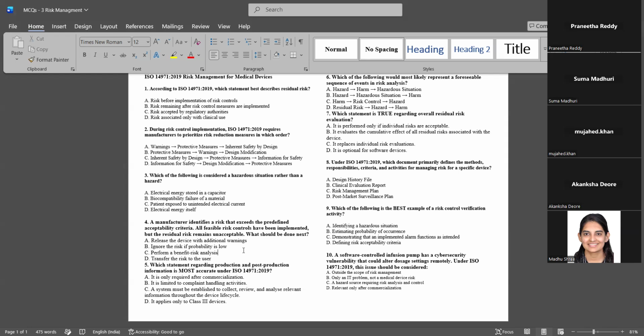Second, it should come as a precaution. Third, it should come as a contraindication. Because this residual risk, at the end of the day, in a clinical scenario, comes as adverse events or complaints, serious adverse events. So it should be given in the warnings. You don't write in the IFU that it has a residual risk, but you know what that residual risk turns into in a clinical scenario. What will be the adverse event?